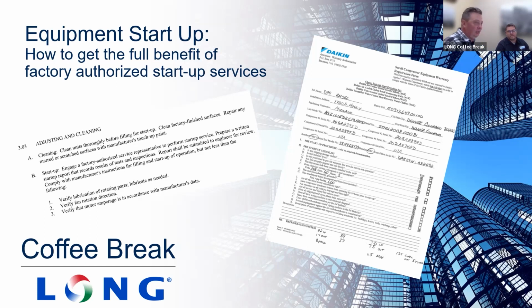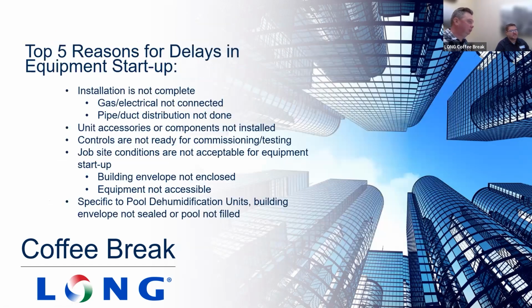Thanks, Rick. If you could just kind of lead us through some of the things to avoid, please. So some of the key components to a successful startup are ensuring that the installation is in fact complete, that the unit's on the curb, that the ductwork's connected, that the controls are as close to ready as possible, that the necessary controls components of the machine, like discharge air temp sensors, are landed in the proper location per the installation manual. Gas pipe is connected and operable. Basically the installation needs to be completed entirely so that we can start the unit and commission it with the controls contractor so that you can avoid commissioning delays.